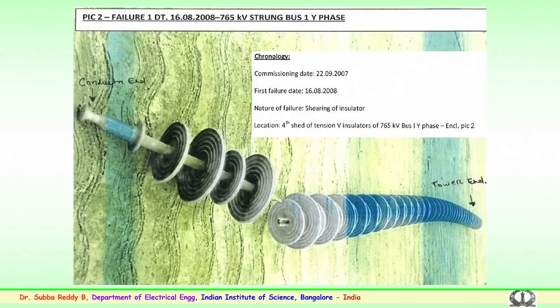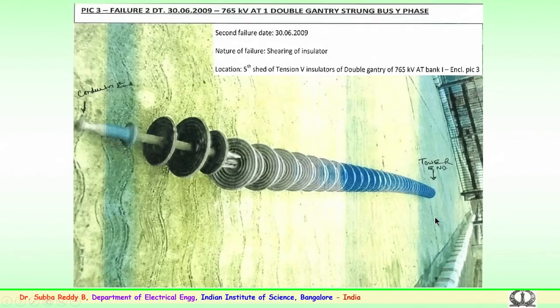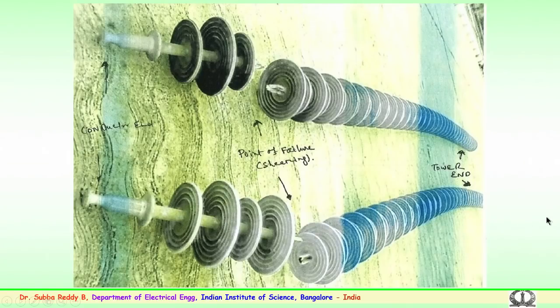There are some failures even in the country which are reported. I would like to explain this for the EHV insulators, where failures have happened at various junctions. You can see one of the failures is because of a brittle fracture which happened after the 5th or 4th shed here, in the country. Similarly, you can see the failure happened at the 3rd insulator, this is a polymeric insulator, where it has happened after the 3rd insulator. So, there are failures which have happened immediately after the stringing, within a year or so. This again is a very serious concern.